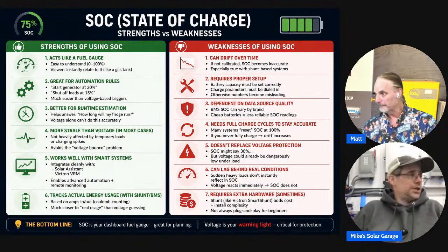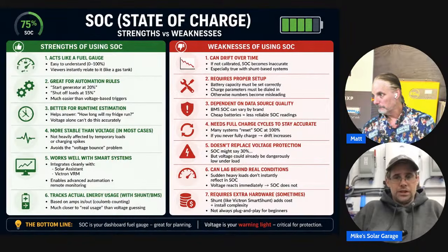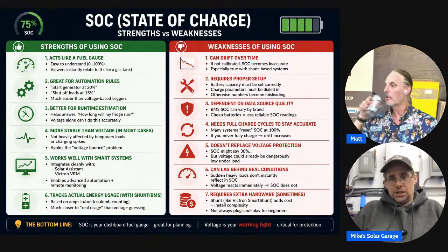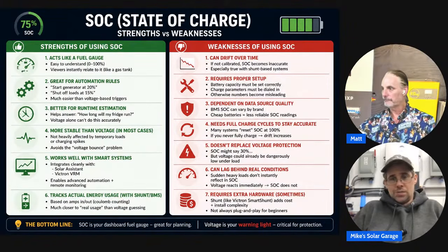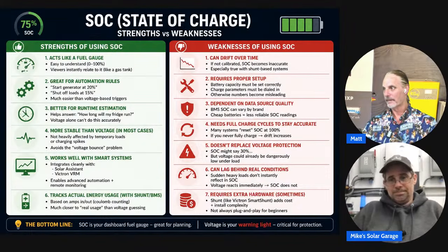That was part of the issue I had last year with the lead times. I ended up bricking 2 batteries without realizing it, and they were on 2 different strings. My setup was saying it's regular, 54 volts charged, but I noticed my capacity was down a good 20% and couldn't figure it out. Turned out 2 of the batteries on different strings were bricked, and there's no way to know just by looking at the voltage of the overall system.